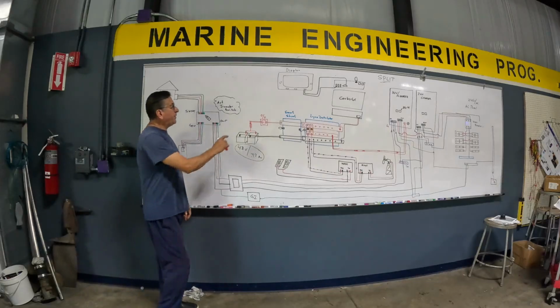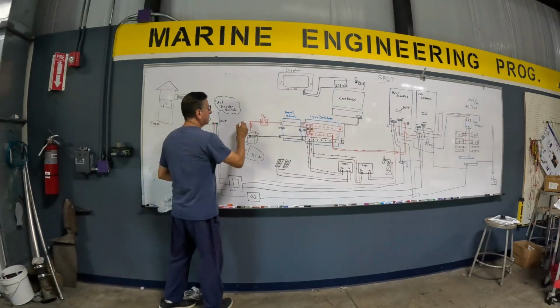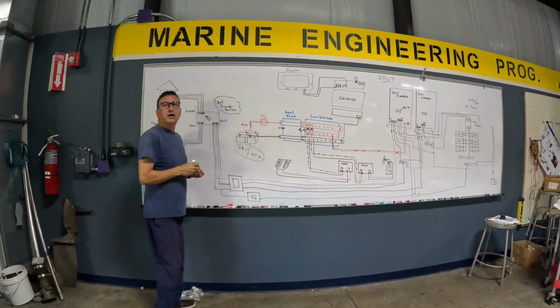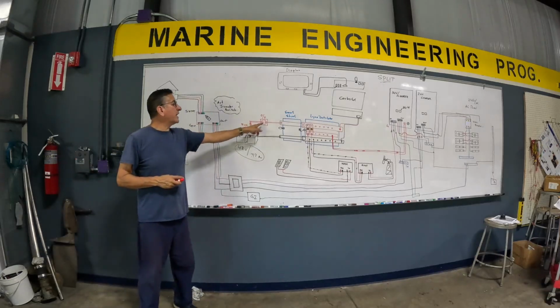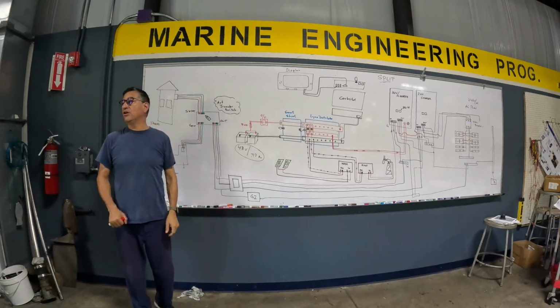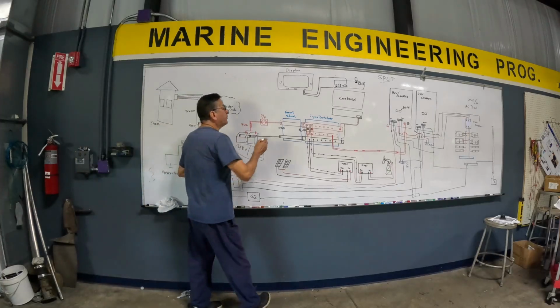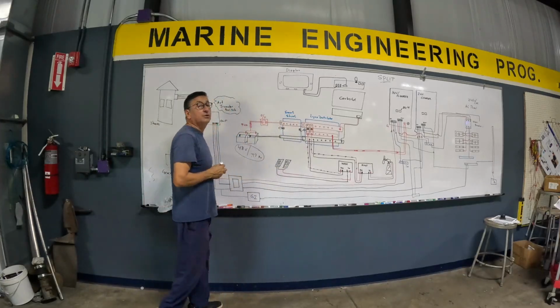All right. The positive output passes first through a big fuse. That's the fuse. And after that it passes through an on-off battery switch, with the capacity according to the capacity of the fuse. Exactly the same. And after that it enters the positive bus bar of the smart shunt. That's the positive bus bar of the smart shunt.